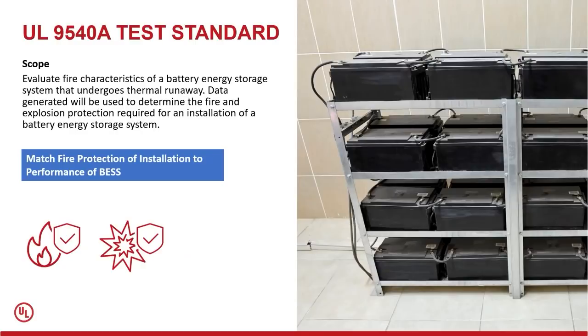UL does not certify a product to UL 9540A. 9540A is a test methodology to develop the information or data that the manufacturer or building owner can then use to engage a fire protection engineer to develop the appropriate fire protection system.